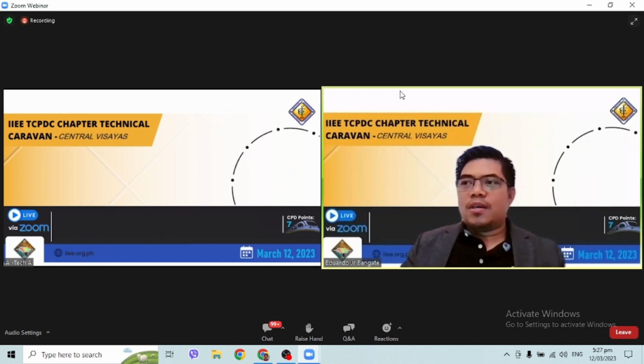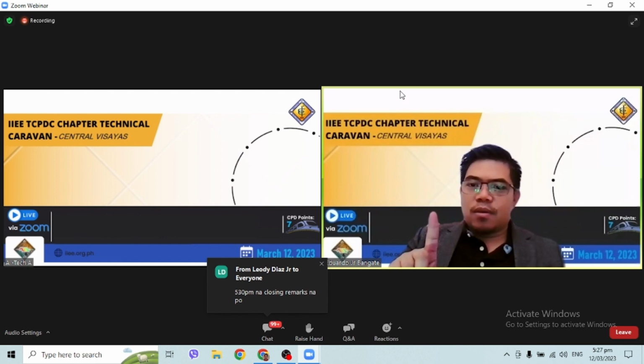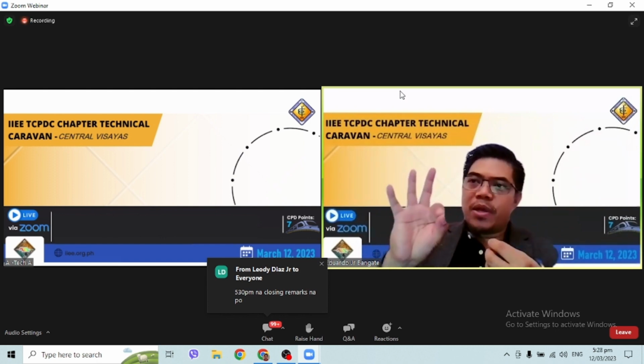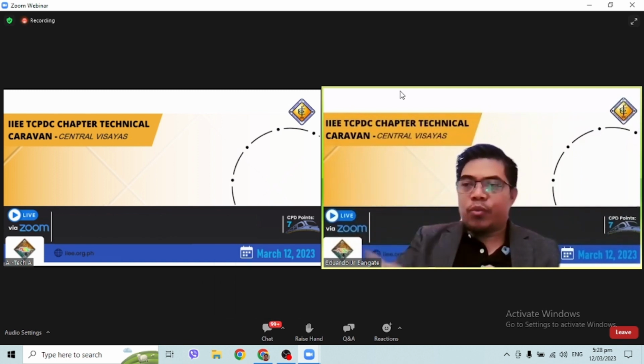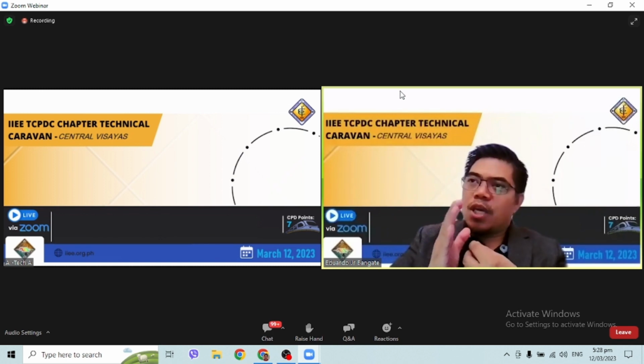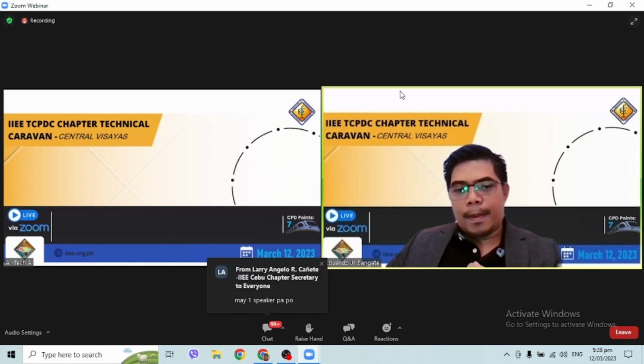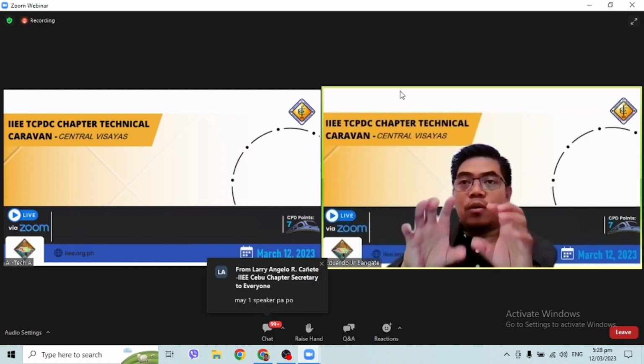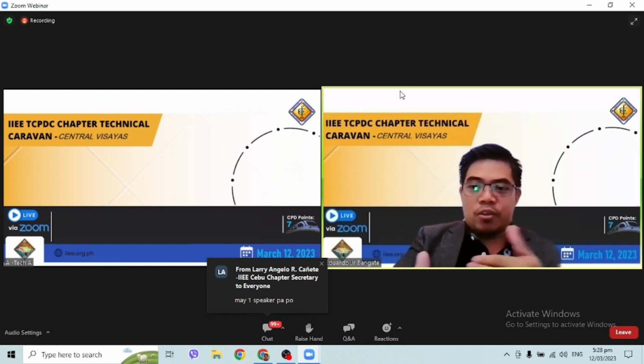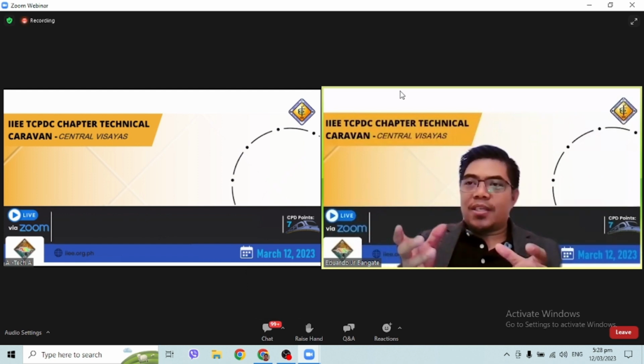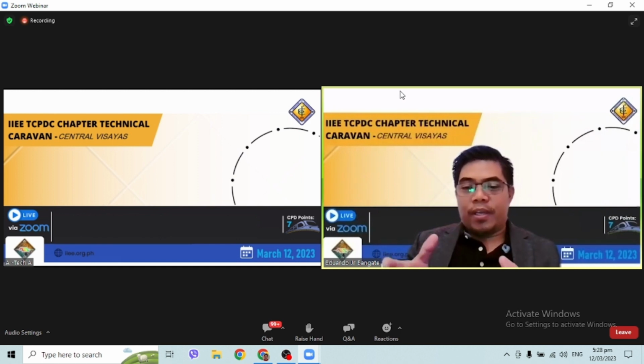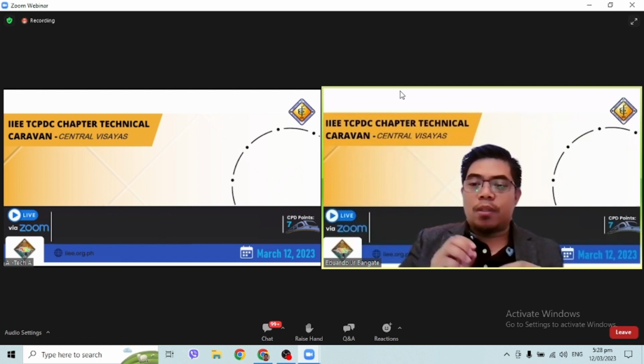Okay. Is the one generator capable of holding one continuous load? If it is capable at 70 to 80%, which one you set, 62, 70, it's up to you, then if one generator is capable of carrying it alone, it will deload again the second generator and stop it. Okay? And then because you are now loading the biggest size of your load, as the question was, it means that this single generator is capable of carrying all the load, the biggest load, by itself alone. Now you will not be consuming too much fuel. You will be doing it economically.